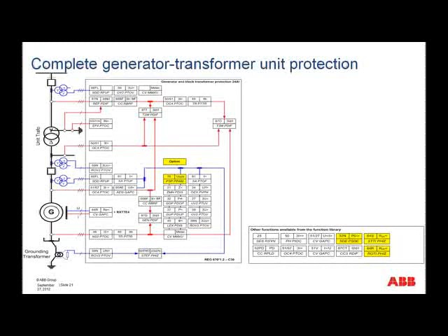Okay, so if we have a look here, this bottom part is pretty much the same protection of the generator. We have the 87G, and now we have the complete protection for the transformer, which includes the 87N or restricted earth fault. We have the 87T. So now this is not an 87O. It's actually 87T. So you can see the zone of measurement is the transformer. It is not including the generator. But then it's also possible to put in another 87O, to give overall differential protection for the combined generator and transformer. And we can also have this overcurrent function that is the backup function for what is connected further down this buswork here.